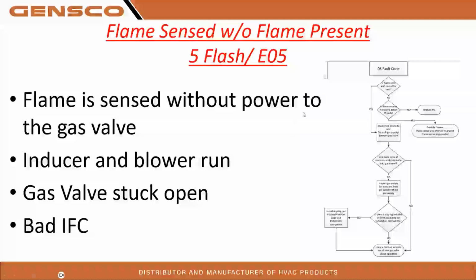So really what you're going to want to do is utilize the service facts and get this information out of here. So you can see on the S9V furnace, giving you a very nice call out saying, okay, we have a 5 flash. So has the flame been seen with no call for heat, no or yes? And you're simply going to move down these charts to be able to help diagnose this stuff.